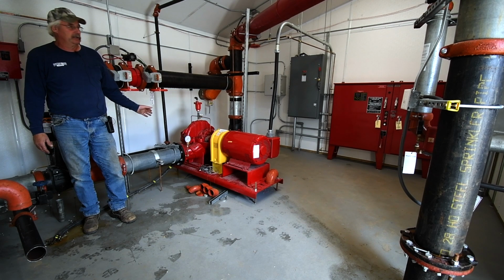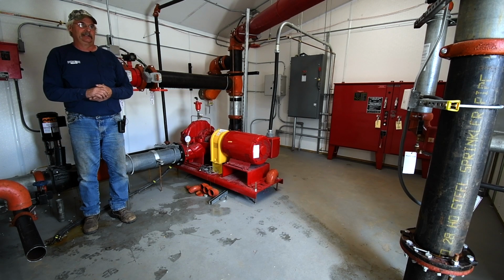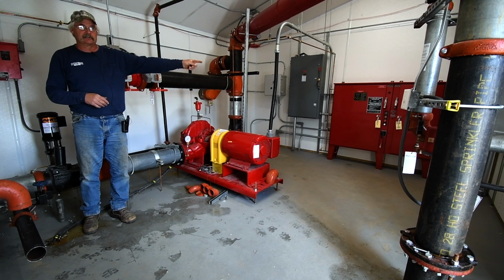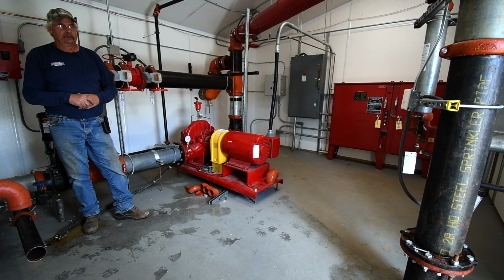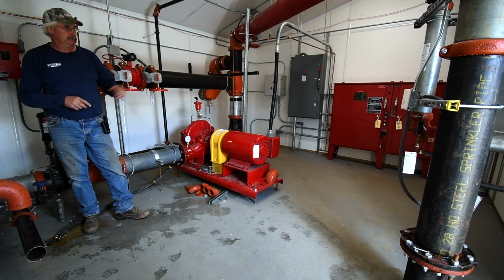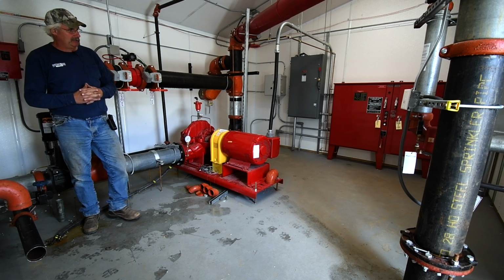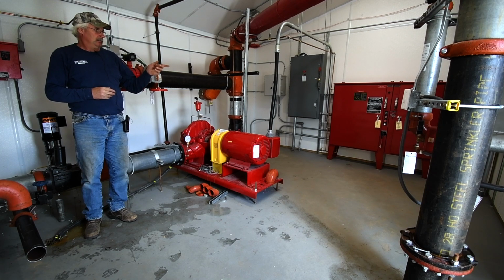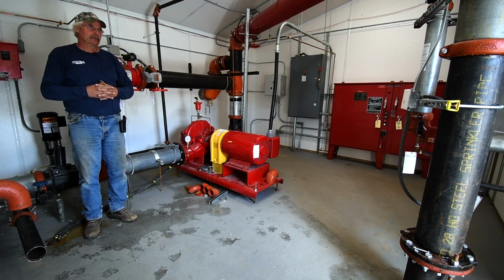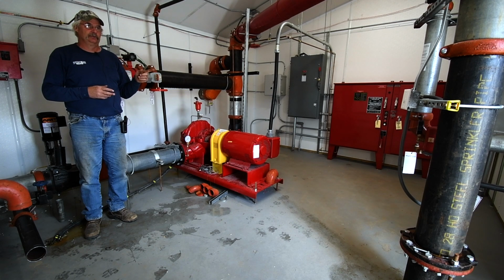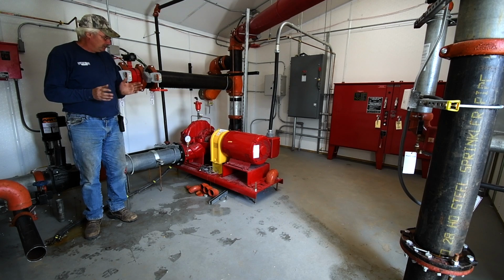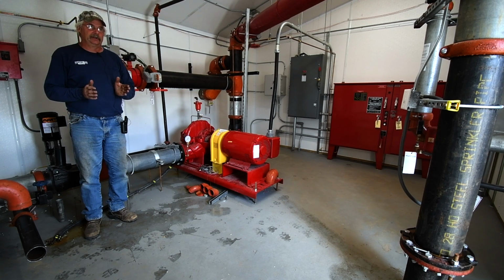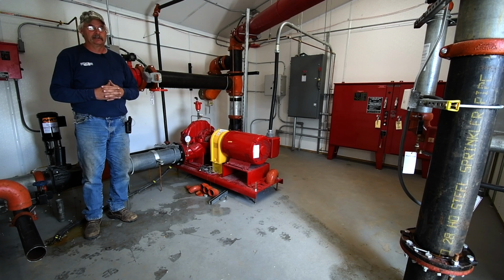Anytime that the fire pump is running, the panel picks it up. Anytime somebody shuts the power off on the disconnects on the 2 controllers on the east wall here, the panel will pick it up. If we have phase reversal, the panel will pick it up. If we have temperature loss, the panel will pick it up. Anytime that there's AC power loss, the panel on the east wall is a dual disconnect panel, which means it's tied to the new generator right outside the door here. So in the event of a power loss and you have a fire issue, the diesel generator is tied together and it will kick on. And that's been certified and tested also.